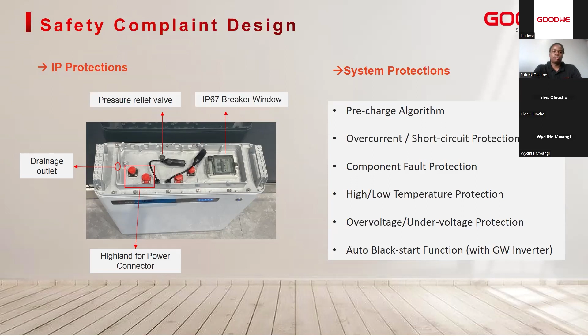In terms of system protections, GoodWe has incorporated a pre-charge algorithm within the Link-SOMU battery. And apart from that, we have overcurrent and short circuit protection and component fault protection. Temperature monitoring of the battery itself, we talked about the cell balancing, temperature balancing. And yes, high and low temperatures are also monitored to ensure it's operating within the stipulated temperatures. Overvoltage and undervoltage are monitored, and protection levels are integrated to prevent any battery failures. And we do incorporate the auto black start function in the Link-SOMU battery as well.